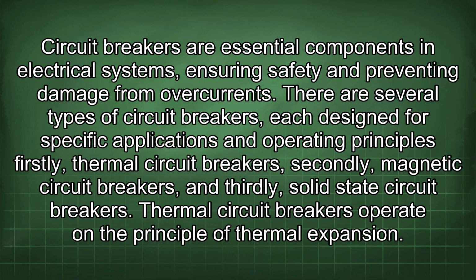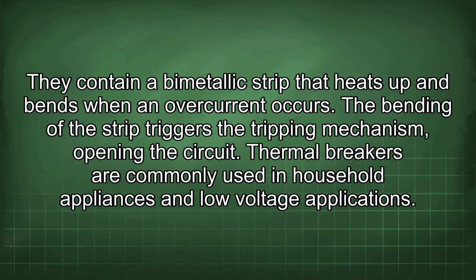Thermal circuit breakers operate on the principle of thermal expansion. They contain a bimetallic strip that heats up and bends when an overcurrent occurs. The bending of the strip triggers the tripping mechanism, opening the circuit. Thermal breakers are commonly used in household appliances and low-voltage applications.